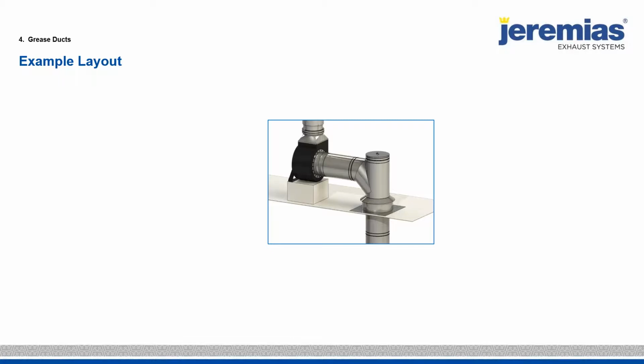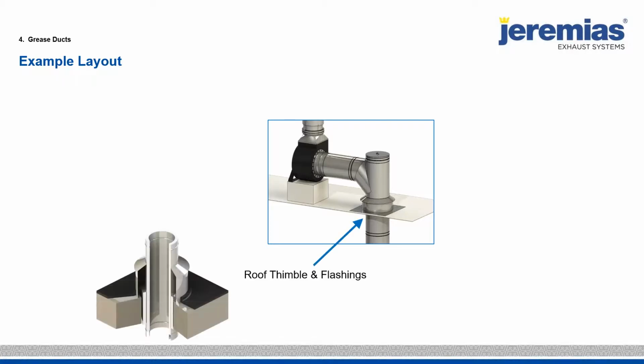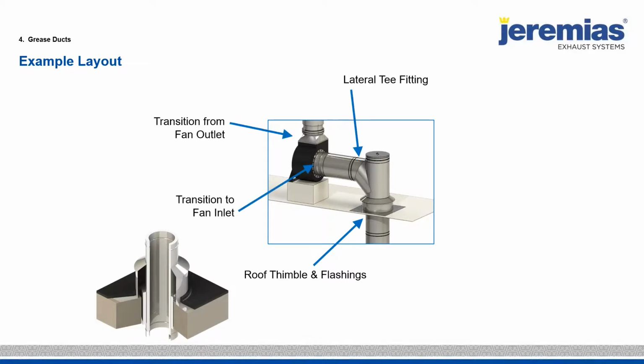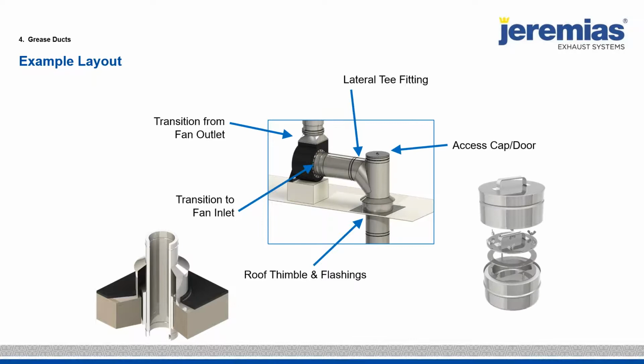And then when you get into large ducts, especially the rectangulars, typically anything larger than 20 by 20 or 22 by 22, you can have a man access to eliminate all the access panels. So we have the roof penetrations. In this case, this could be maybe a 24-inch diameter duct where we have a single access at the top going all the way down.